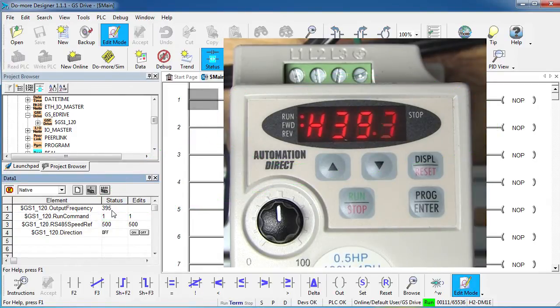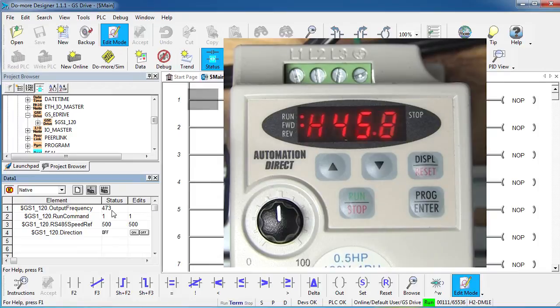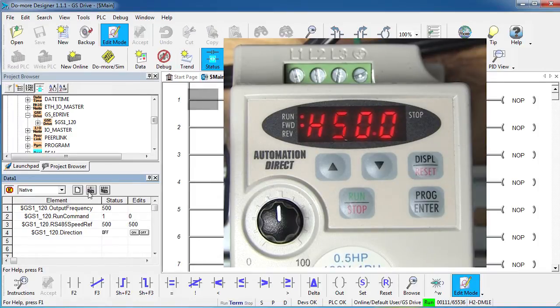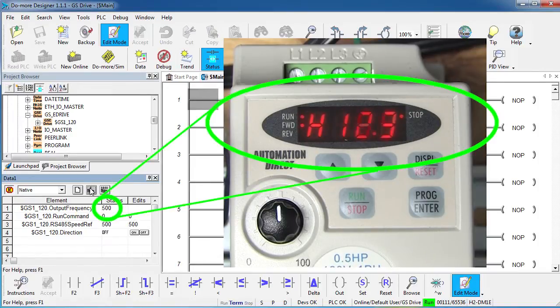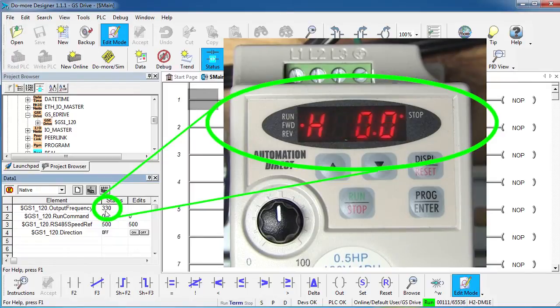I have a long acceleration time set up right now so you all can see this ramp up. If I put a 0 in here, that says stop the drive and sure enough the drive ramps down to 0.